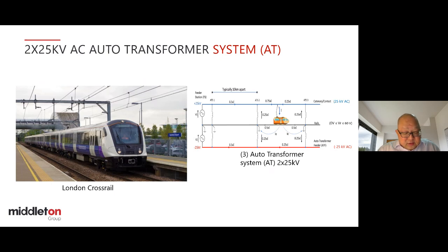Now, what are the cons? Again, it is more expensive than the booster and return conductor system, with additional equipment. So you have auto transformers at 10 kilometer intervals, and they need switchgear and also land along the alignment for the auto transformer station. Obviously, again, there's more maintenance for the equipment. Next slide, please.